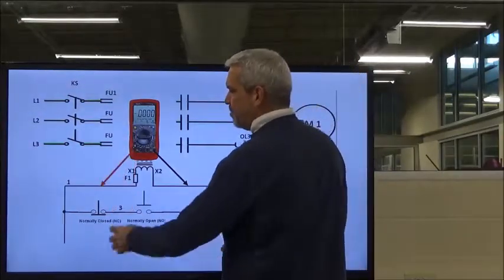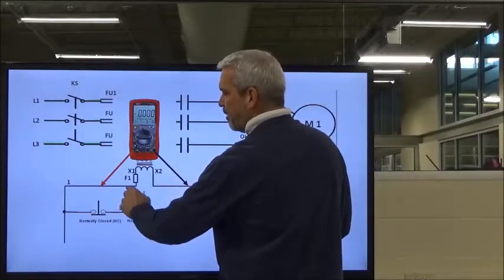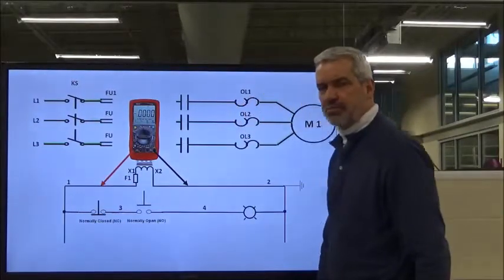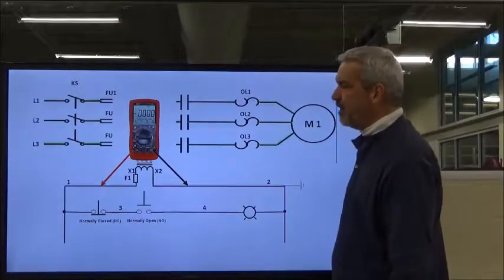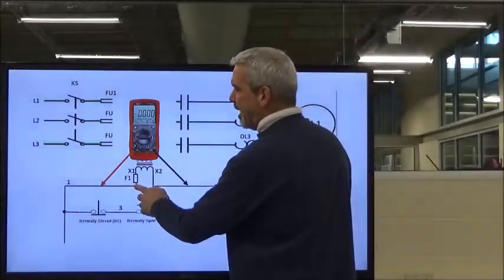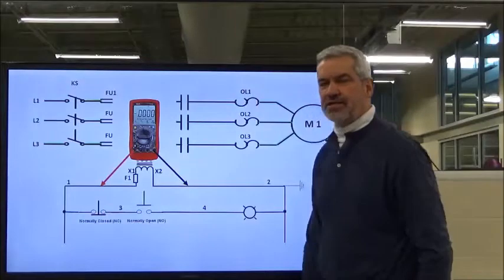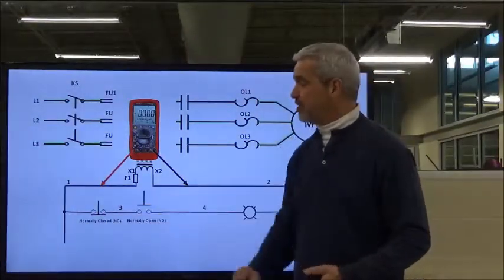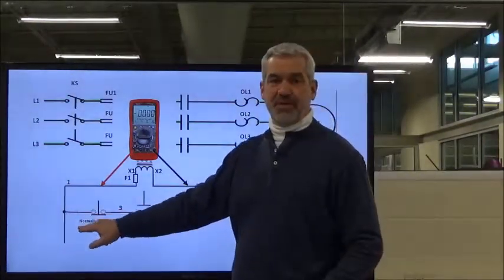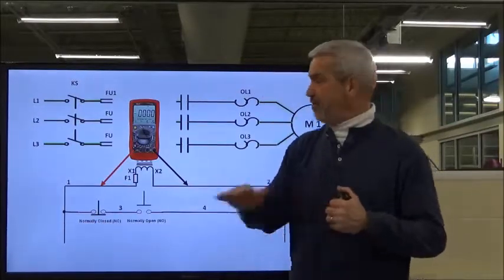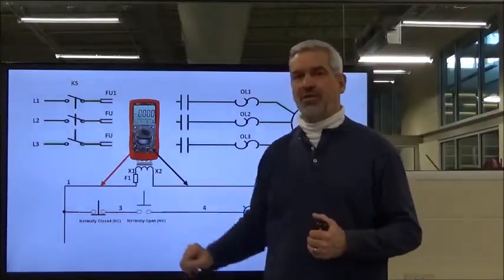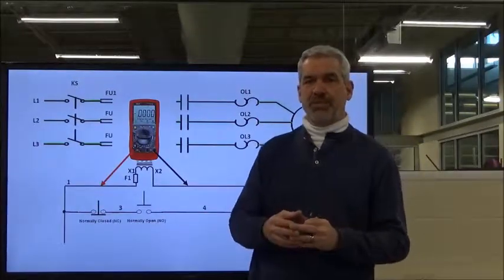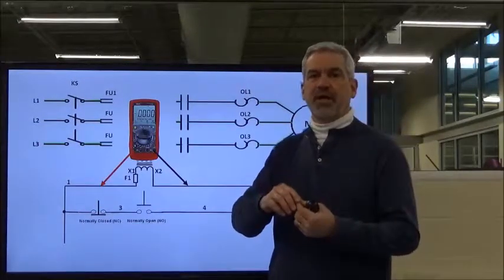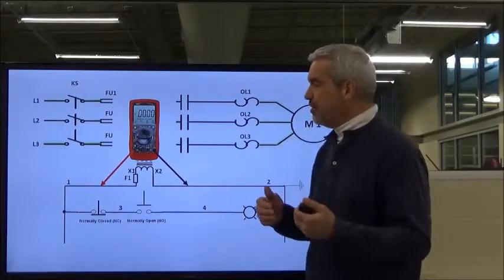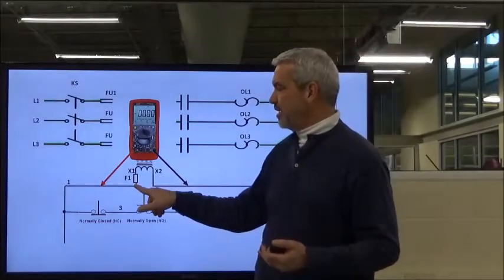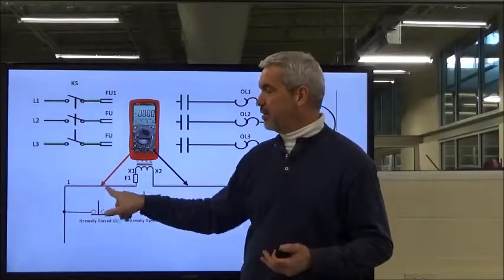And then I'm going to go to this point here where my first device in line is my normally closed switch. But we can't automatically assume that we've got voltage on that switch. That switch could be 50 feet away. And in between this point and the switch could be a junction box, could be terminals, wire terminals, or wire nuts that have come loose. So we can't naturally assume that because it's coming out here, we've automatically got it there. There could be something in the way.